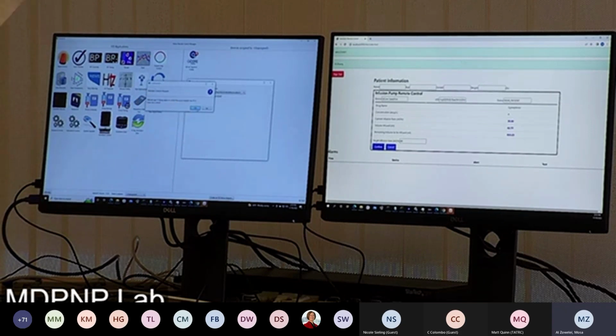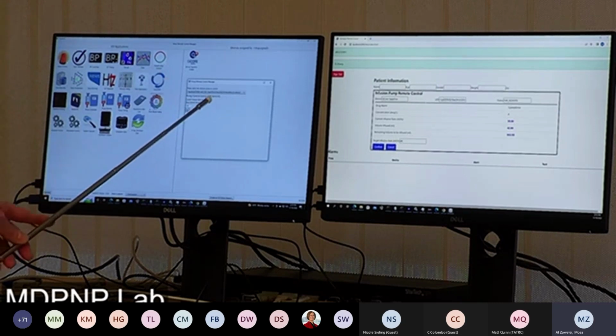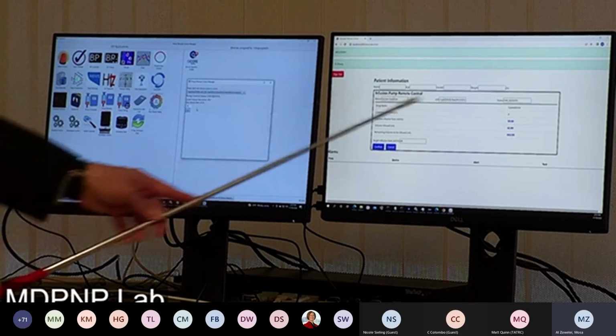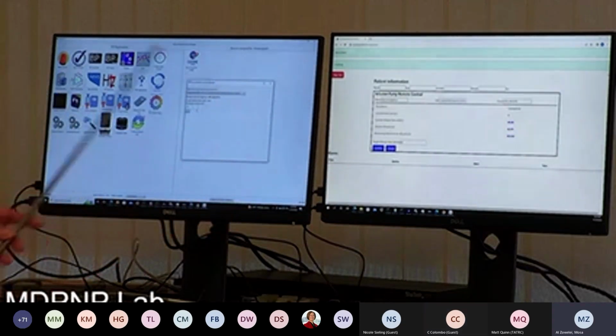So we'll go through, click yes to grant control. That will then allow that rate of 40 to get pushed through to the pump. And the pump control status here changes to far remote. And that's reflected in both places. They both agree that the pump is under far remote control.